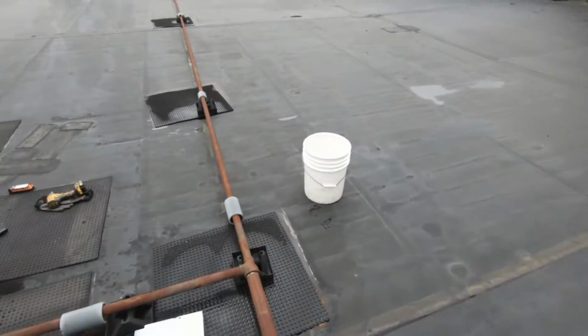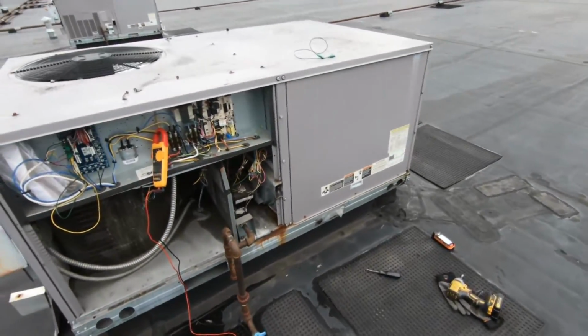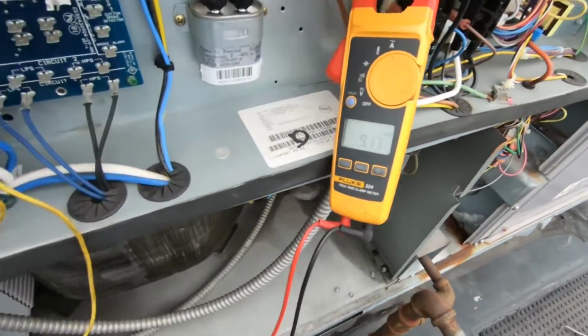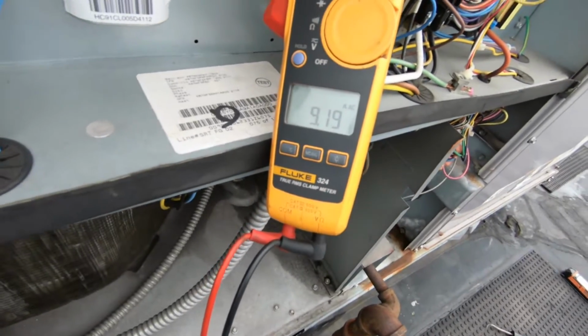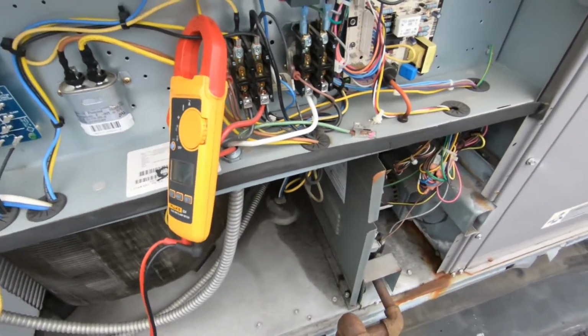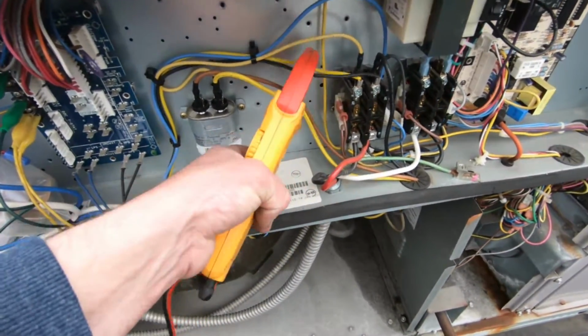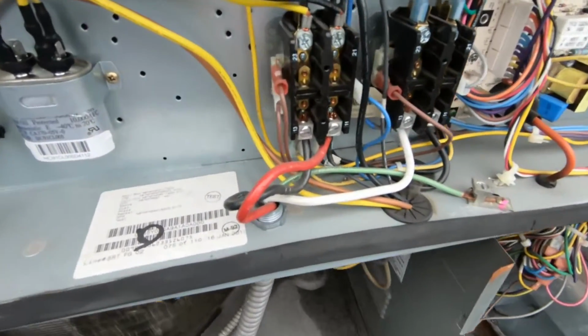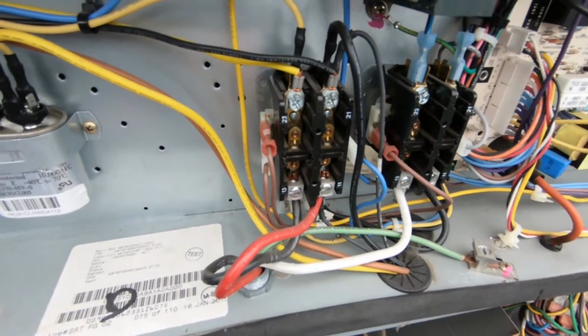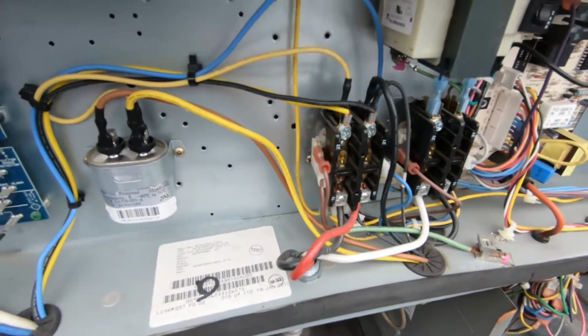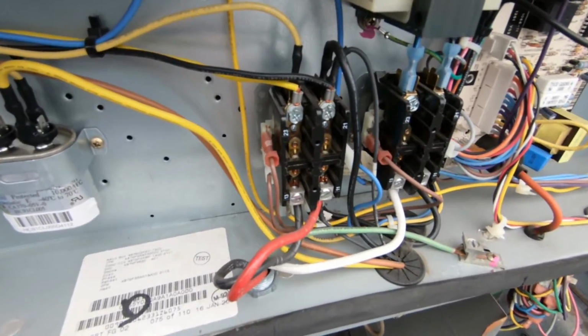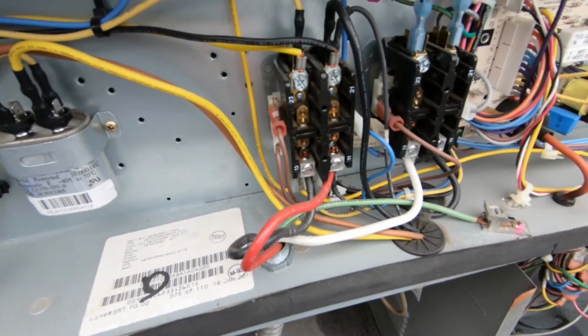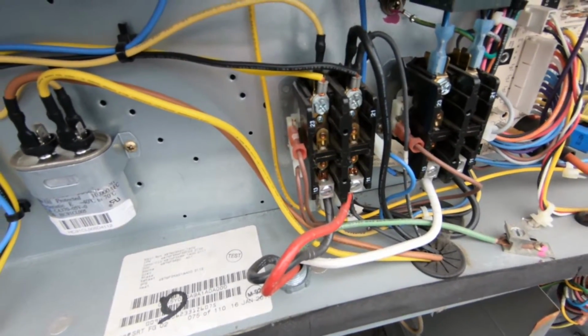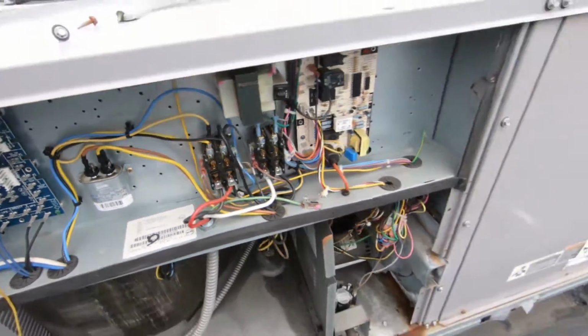It's not real warm inside the store. It's only 65 degrees out. We're running 9 amps, but our compressor contactor's chattering. Not a regular chatter, just kind of every once in a while, you know. There it goes.